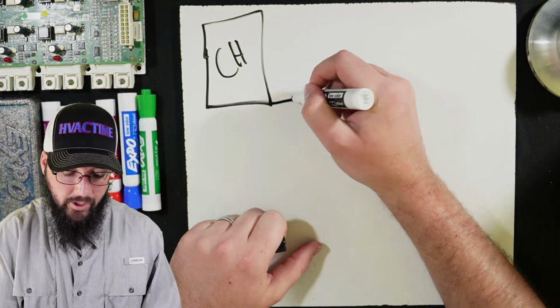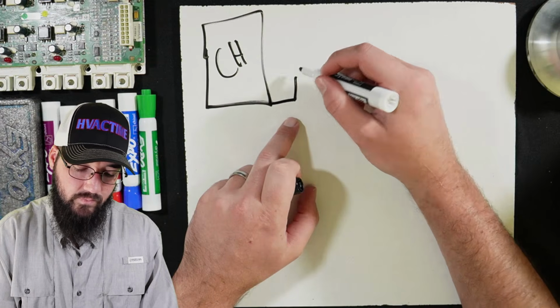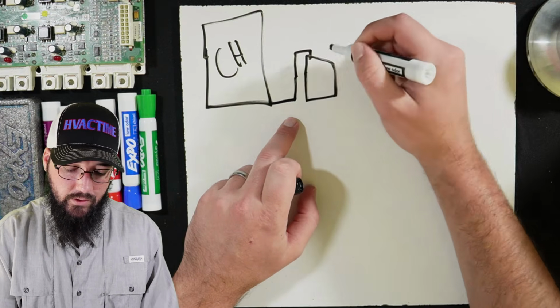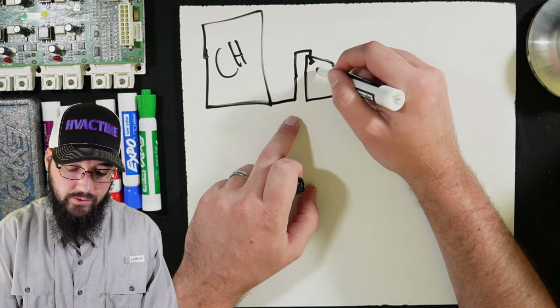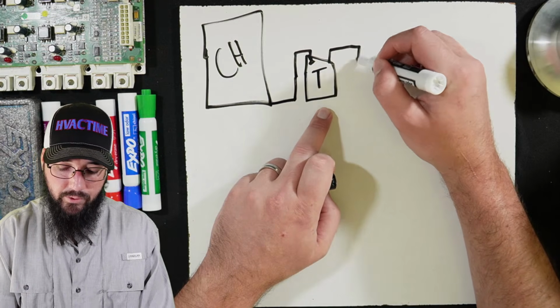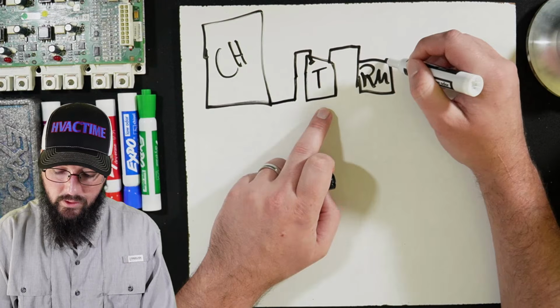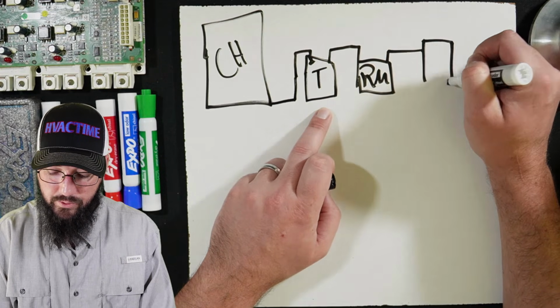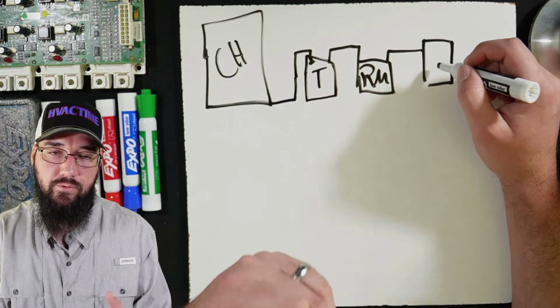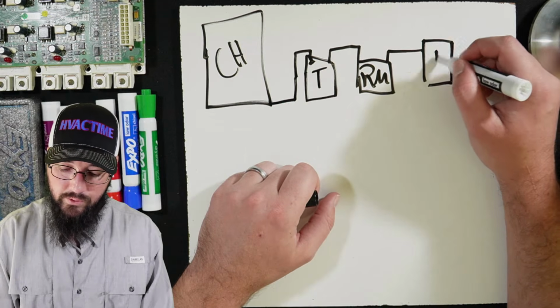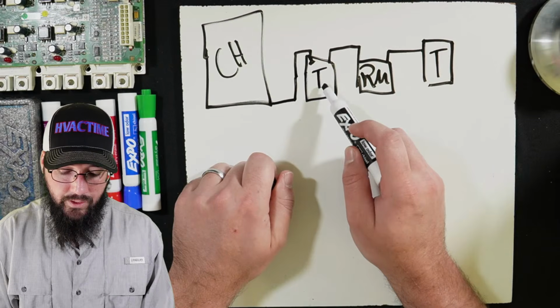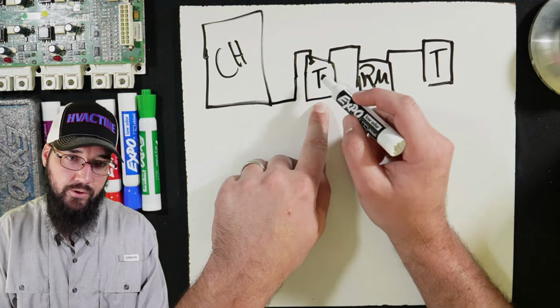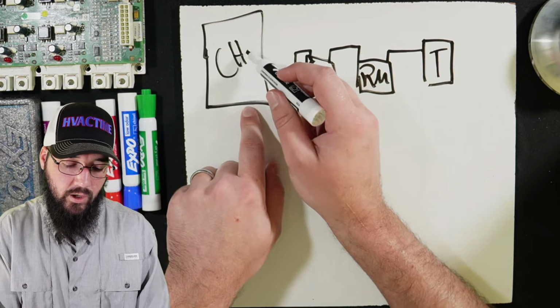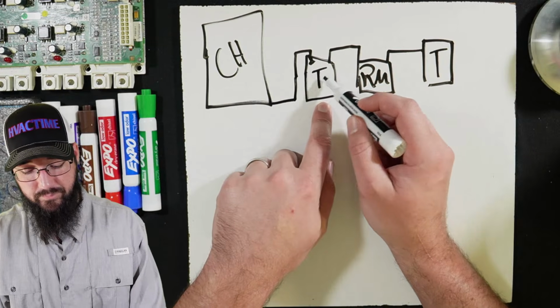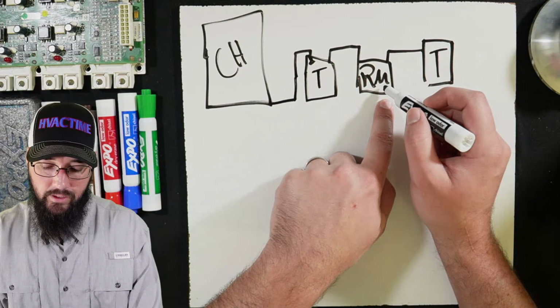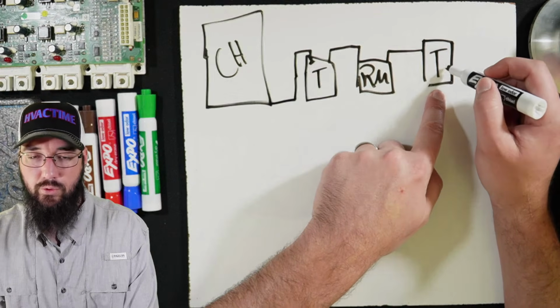If this is our chiller, we're pulling out of a liquid recovery port on the evaporator. We're coming into the liquid line on this recovery cylinder, and coming out of its vapor port into the recovery machine. Then we come out of the recovery machine into a vapor tank, so this only captures the vapor coming off the recovery machine. The recovery machine draws this recovery cylinder down on its pressure. As the pressure is reduced from the vapor port, it drops lower than the chiller. The chiller naturally feeds liquid refrigerant into this tank, out through the vapor port to the recovery machine, and then into our vapor capture tank.